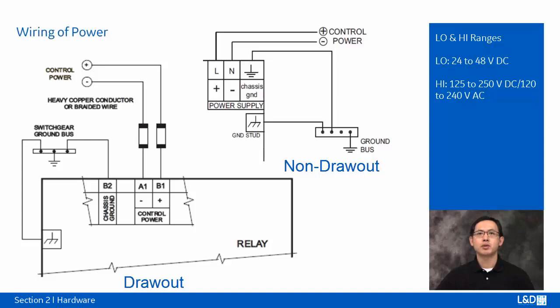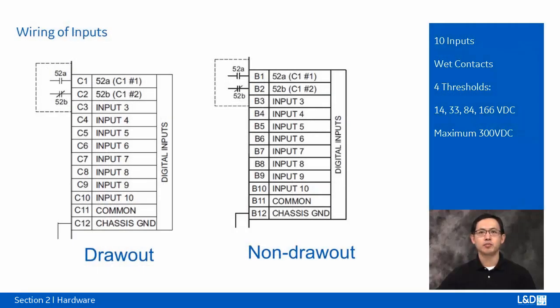Power. The power supply to the drawout type relay is wired to terminals A1 and B1 and grounded on B2. For the non-drawout, the power supply is wired to terminals L and N. According to the order code of the relay, there are two levels of power supply, low and high. The range for the low power supply is 24 to 48 volts DC, and for the high range is 125 to 250 volts DC or 120 to 240 volts AC. Control power supply to the relay must match the installed power supply range. 3 series relays have 10 digital inputs.